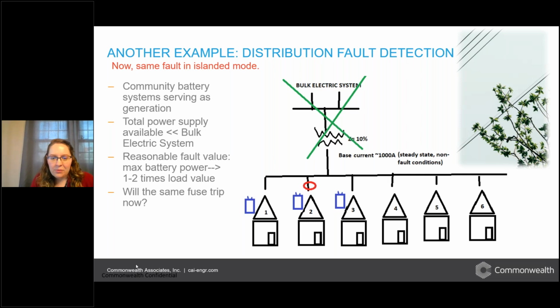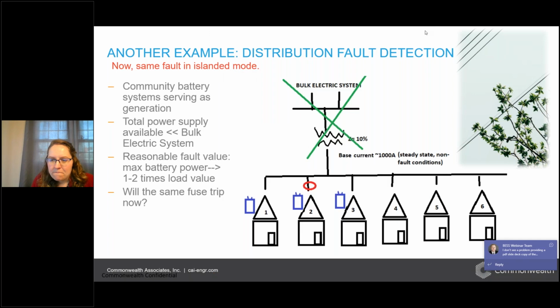But how can a fuse that was there from last week when we were grid connected, sized to look for 10,000 amps, how can that fuse looking for 8,000, 9,000, 10,000 amps know that only 2,000 amps is now a problem? Remember, our base current was around 1,000 amps. So going from 1,000 to 2,000 might not be a significant jump from the perspective of the fuse. So this is the new frontier of the power industry as a result of emerging technologies like inverter-based generation, tapping distribution systems. Regardless, how do we reliably isolate this fault? How can we help our customers with this problem?